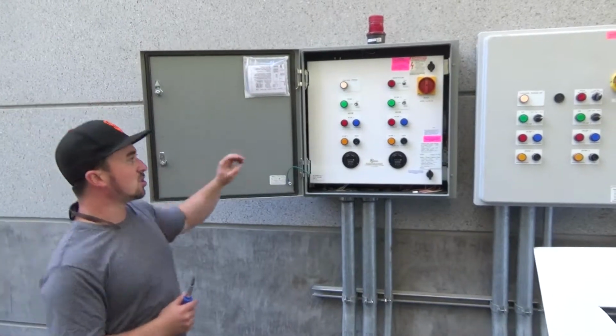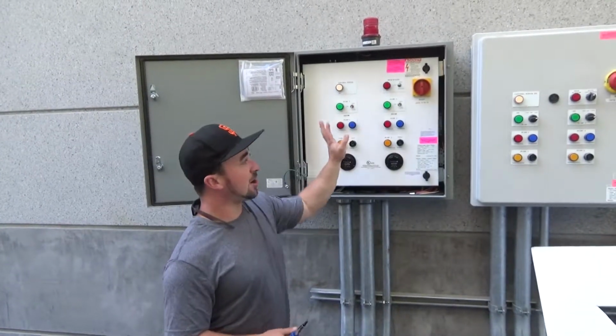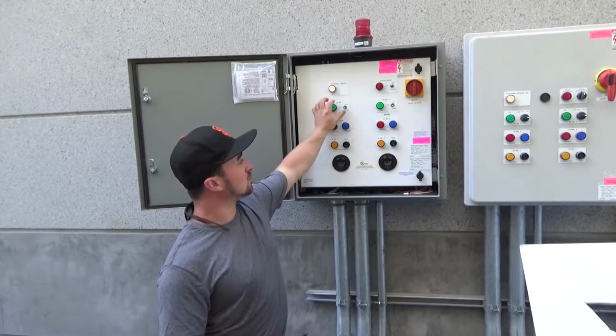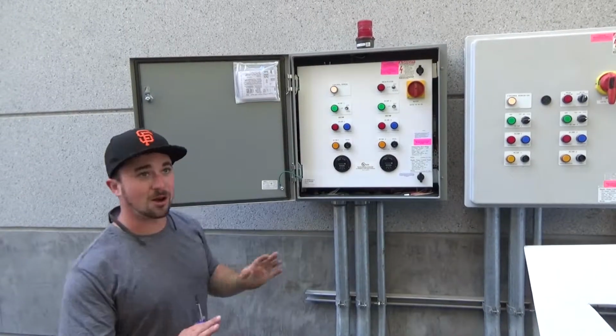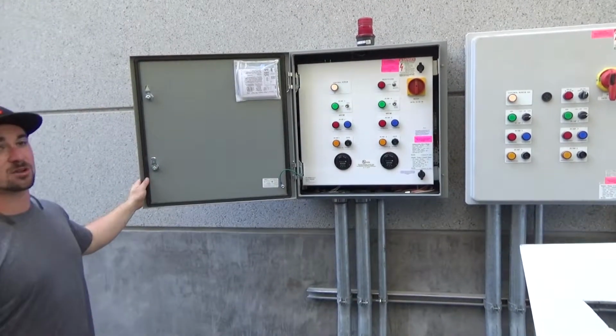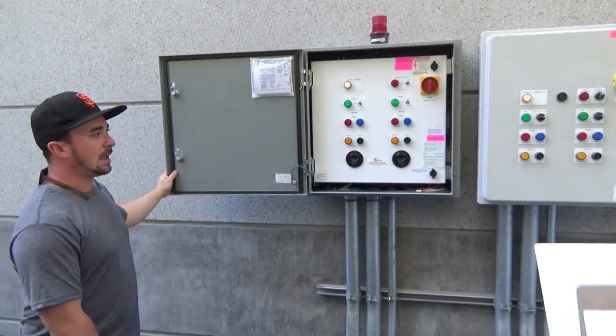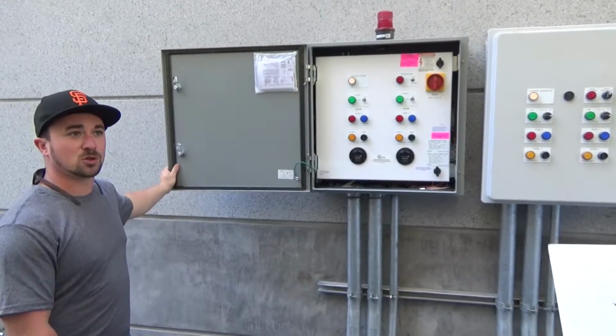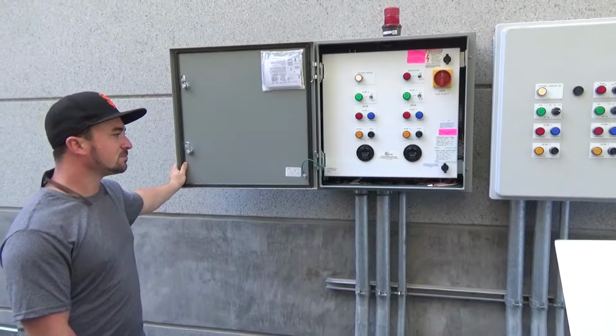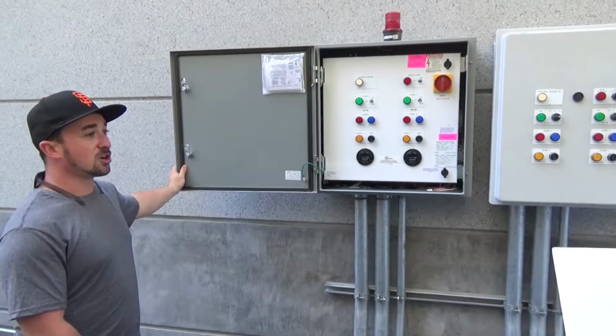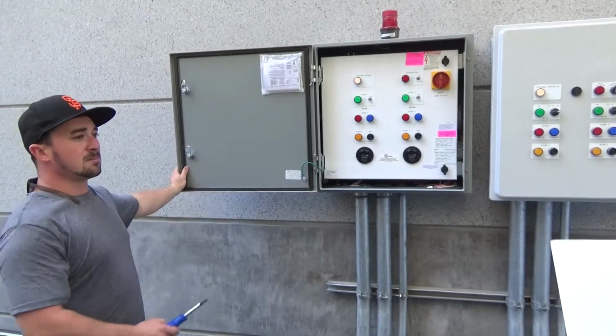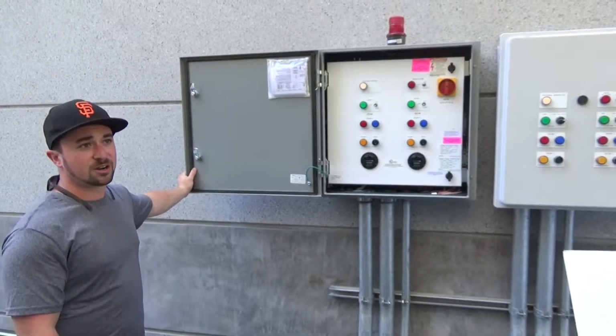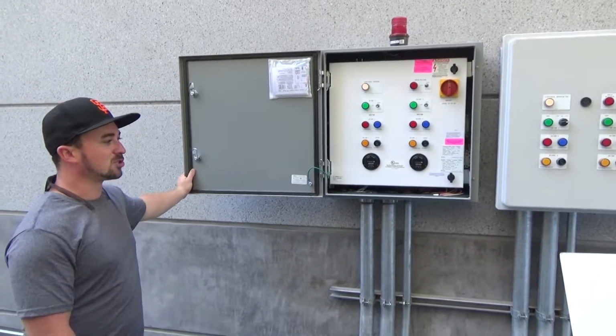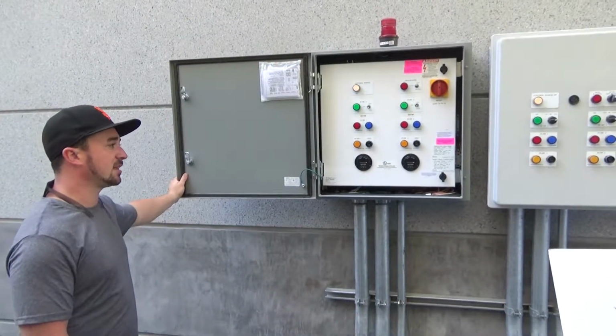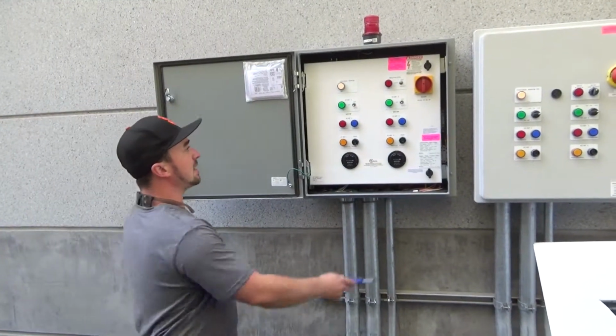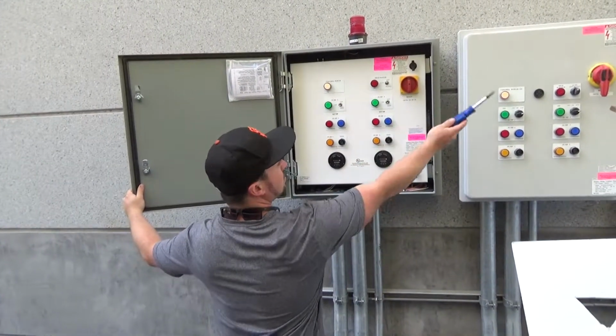So just make sure you guys don't just leave them in auto, and if it doesn't have a call, don't run them dry. Do not run them dry, because again, you'll trip moisture temperature sensors, and it's very bad for the pit. You'll burn seals. It's just bad all the way around. So if you're going to do any sort of test on the pumps, make sure that pit is filled and it has water in it so the pumps aren't running dry and overheating or anything like that. Again, main disconnect.